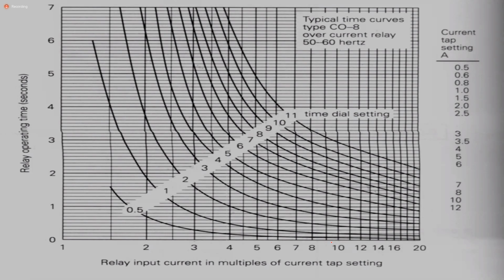Good? All right. Now, next. If you say you understand that, the next one was 10 amperes. With 10 amperes coming in from the CT, and we have to hurry up because I messed up my timing, how long would it take the relay to operate? 0.2 seconds, sir. Sir, if you go across on the center top graph to 10, you meet the curve, which is at 1, sir. So that would be 10 amperes, right?